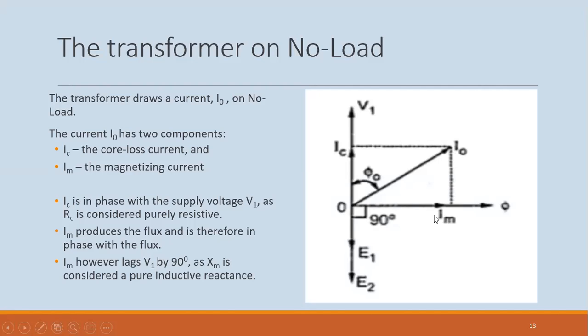That magnetizing current is what produces the magnetizing flux, the flux that flows through the core. So although I0 is a very small current, it has two components: part that produces the flux, and part that supplies the core losses, the eddy current and hysteresis losses.